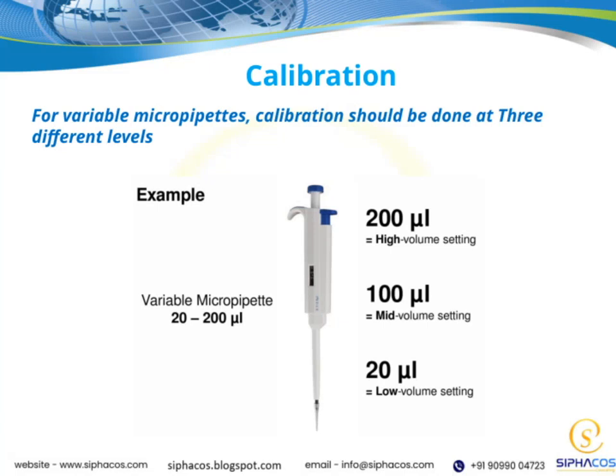Today, I want to focus on the calibration process for variable micropipettes. It's important to understand that calibration isn't a one-time task. It needs to be performed at 3 different levels. This approach ensures accuracy across the entire volume range that the micropipette is designed to handle. First, calibration at the lowest volume level verifies that the pipette dispenses the correct small volumes, which are often the most challenging to measure accurately.